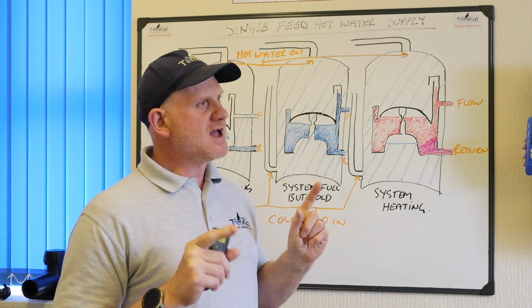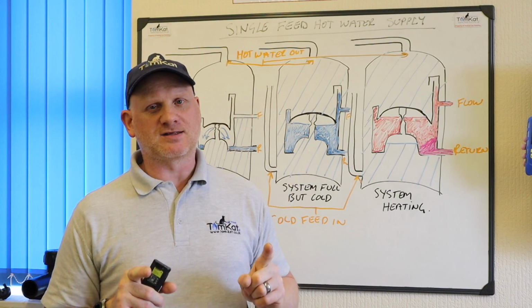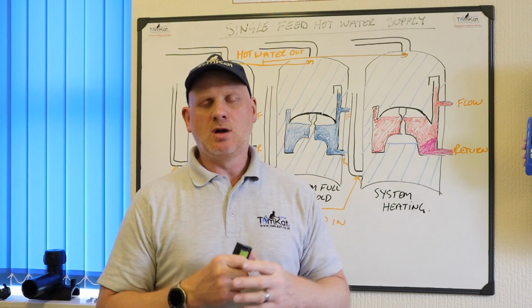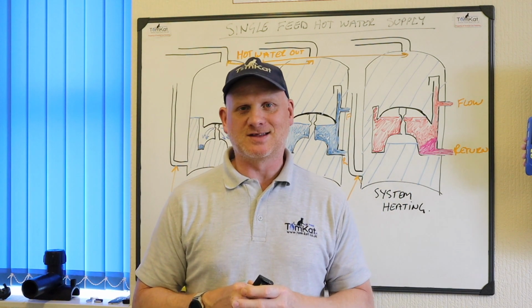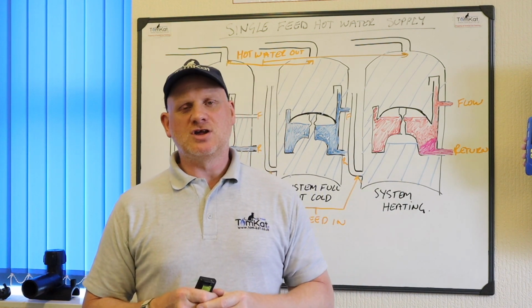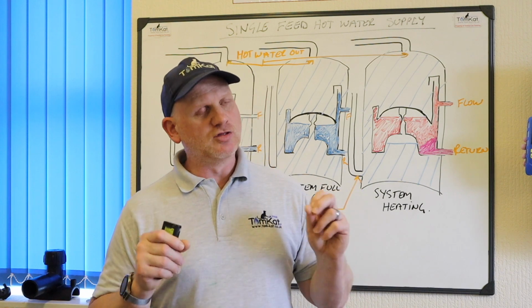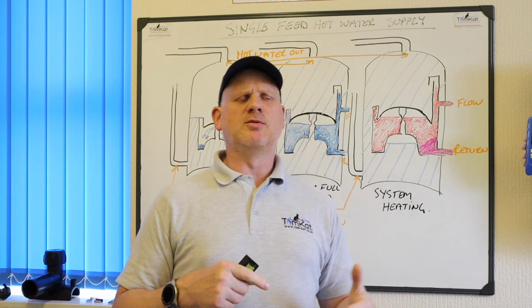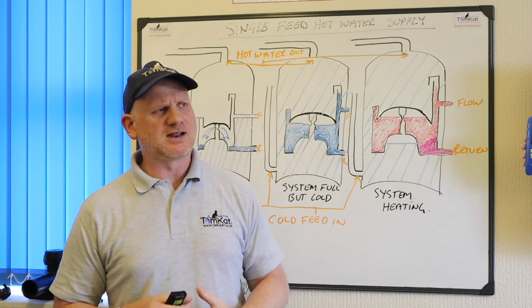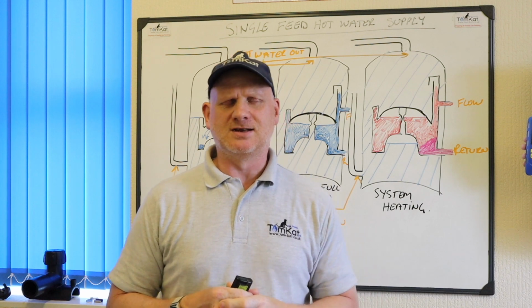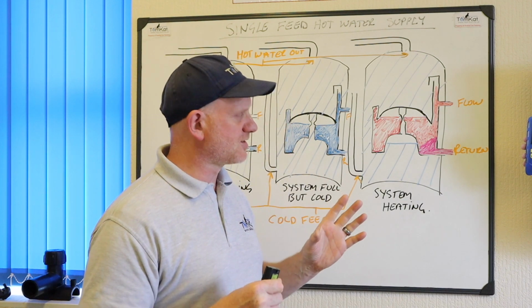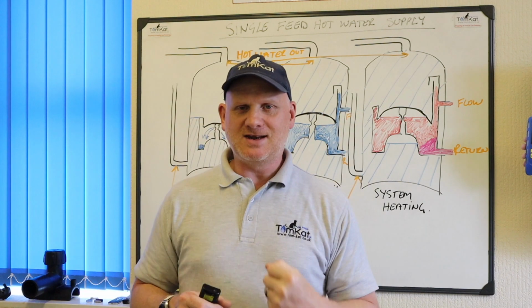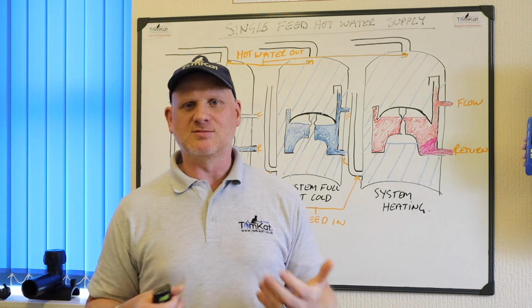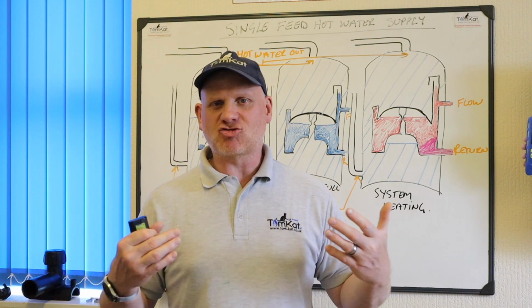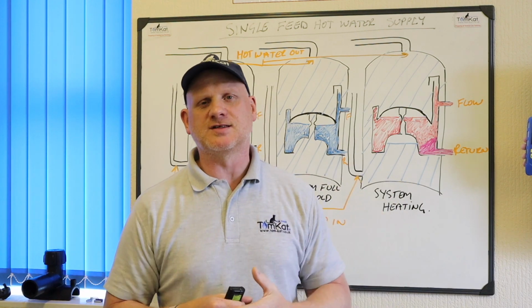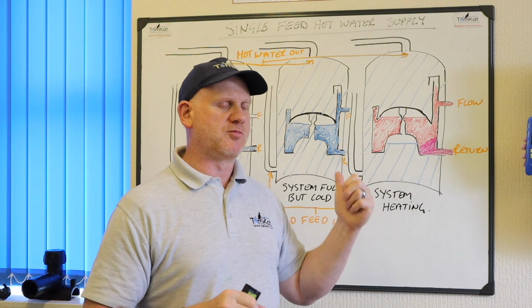So no doing that. The next thing is you cannot upgrade a Primatic cylinder to a fully pumped system, because if you do, you'll break the bubble inside the cylinder, which we'll look at in a minute. One of the other things you can't do is add a lot more radiators onto the Primatic cylinder. So if you get called to a job and they've had an extension done and they want to add more radiators onto the system and they've got a Primatic cylinder, there's every chance it won't work, because as we're going to see in a minute, the bubble inside here is where the expansion for the central heating system takes place. So that's 4% extra, so you're adding more radiators, more water to the system, so the system might be too big for the Primatic cylinder.